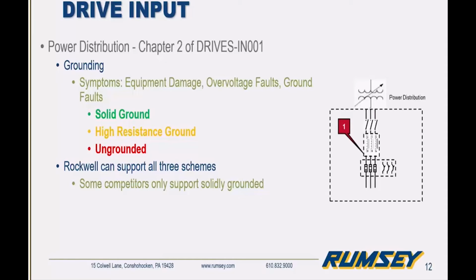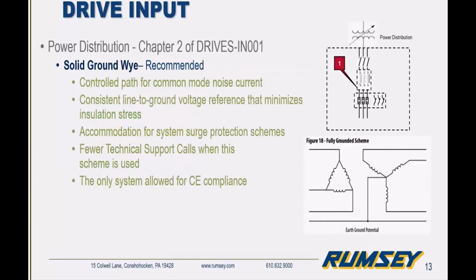Either way, we want to make sure that we understand what the power distribution grounding system is, and make the rest of the necessary adjustments for acquiring the proper grounding in order to basically avoid any equipment damage or overvoltage or ground faults to occur. So the recommended grounded type or grounding scheme to be used will be a solidly grounded system. This is going to be the most reliable solution, and also it's the only system that's really CE compliant.